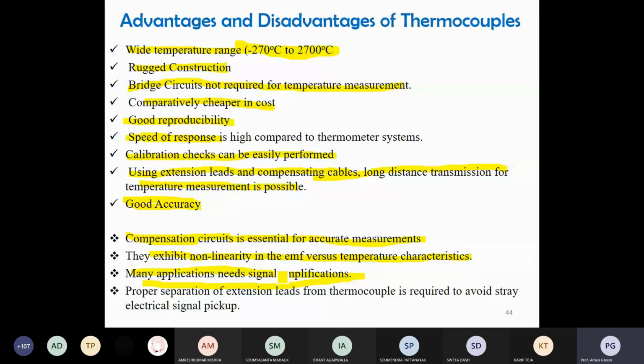Proper separation of the extension lead from the thermocouples is required to avoid stray electrical signal pickup. Stray fields may interfere with the thermocouple's pickup, so external fields can affect your instruments. Keep in mind that there should not be any external field present.